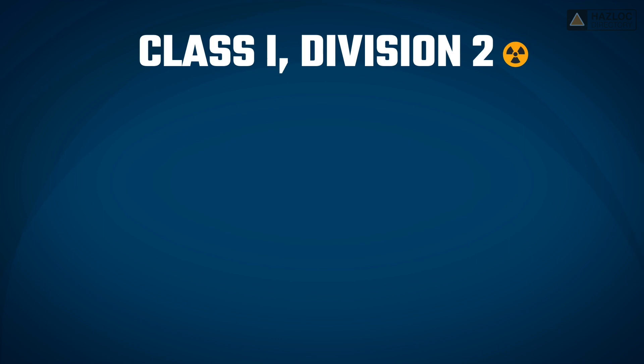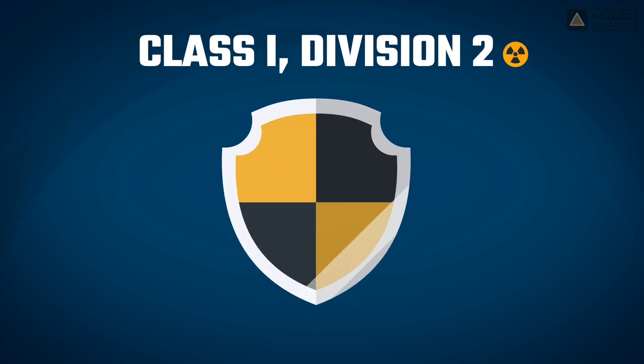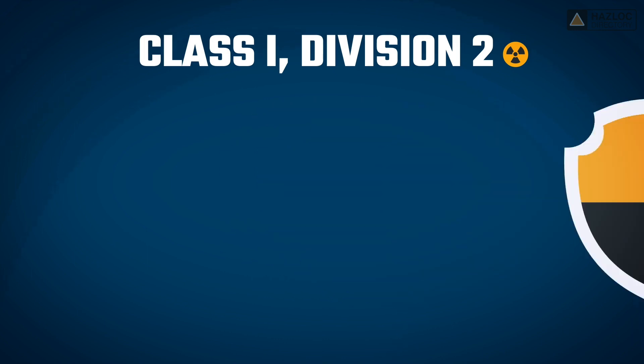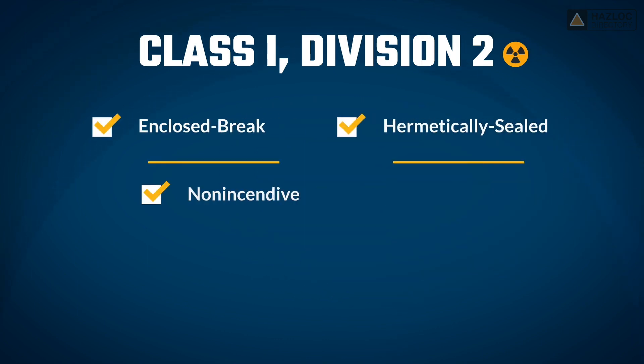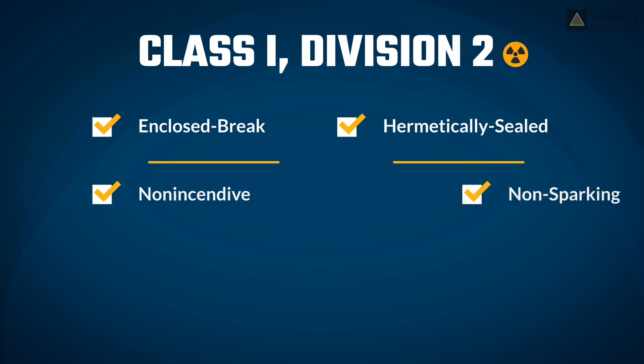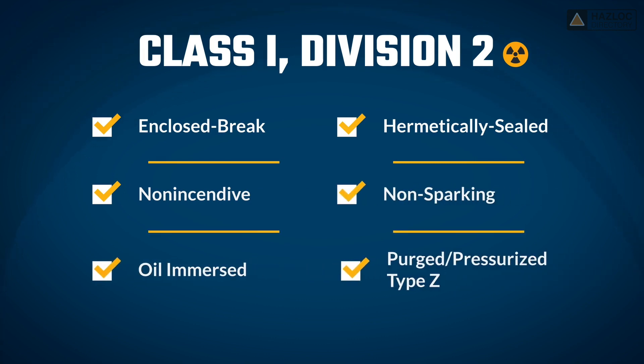In order to be certified as compliant with safety standards for Class 1, Division 2, the product must be protected by one or more of the following protection techniques: enclosed break, hermetically sealed, non-incendive, non-sparking, oil immersed, purged/pressurized Type Z, as well as any of the Class 1, Division 1 protection techniques.